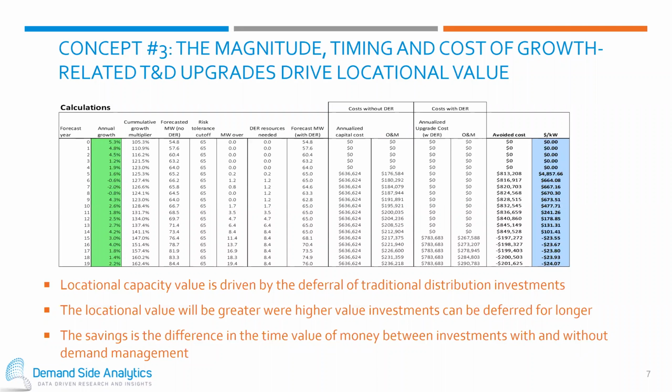The third concept is the valuation. And valuation is typically looked at by comparing, here is the cost of a T&D upgrade, annualized, in terms of how it goes into the rate base. And here it is without the load growth. So you can compare them side by side. In some cases, what we're often doing is comparing and saying what happens if we manage the load growth by something such as distributed energy resources, which can include batteries, energy efficiency, demand response, etc. And you calculate it with and without the additional load, and the savings is really the difference in the time value of money between those investments.